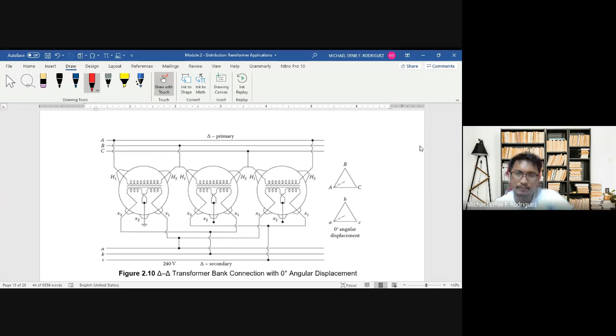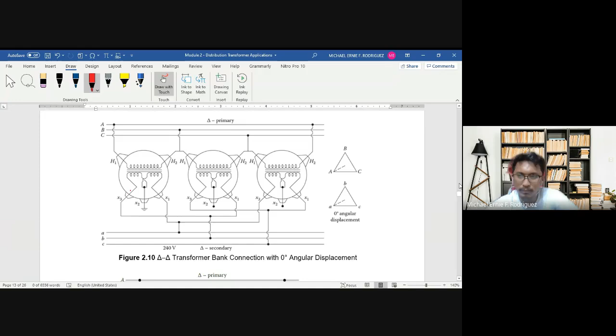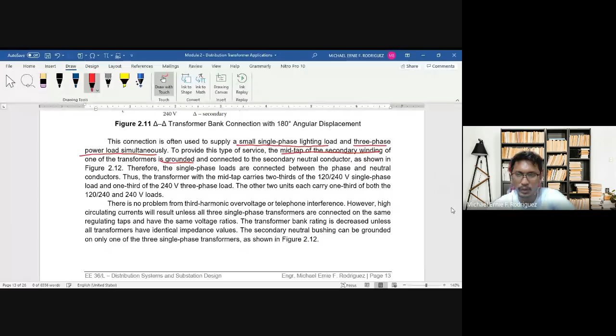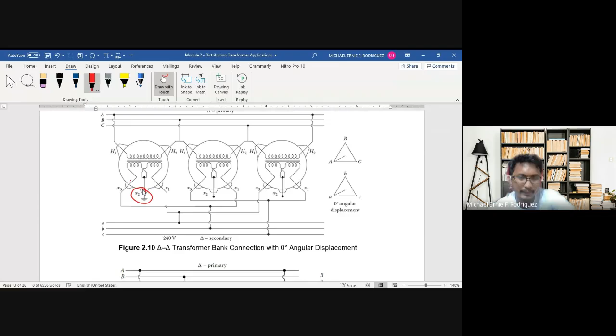What we see here in the module is the schematic diagram or the single line diagram: H1, H2, and then you have your X1, X3. So the transformer is additive. The delta to delta connection is used to supply a small single-phase lighting load and three-phase power load simultaneously. For this service, the mid-tap of the secondary winding is grounded — if you look at the drawing, this mid-tap, X2, is the X2 terminal.